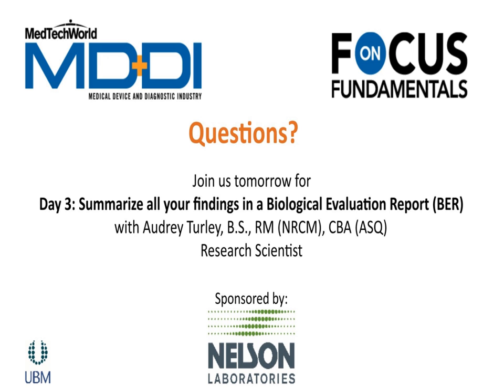So no, generally we don't even quote a toxicological risk assessment until we know what comes off the device. The cost of a toxicological risk assessment is really based on how many compounds need to be fully evaluated. So it's very, very hard to estimate that cost when you have no idea what's going to come off the device and need a full evaluation.